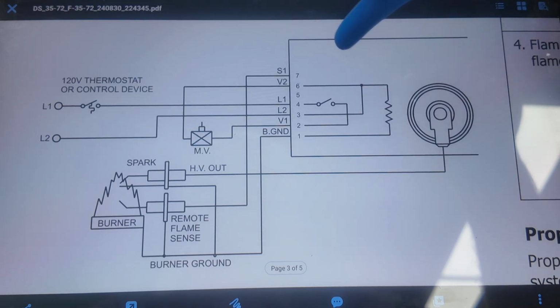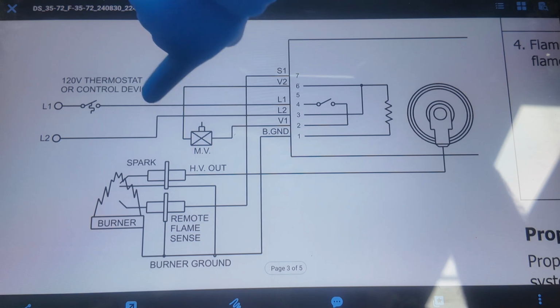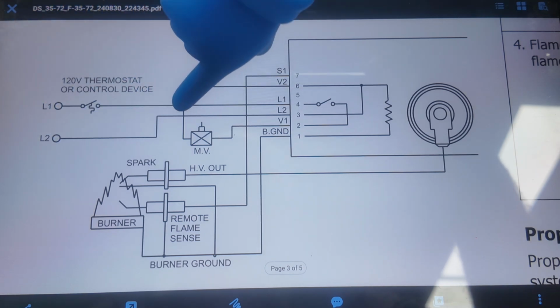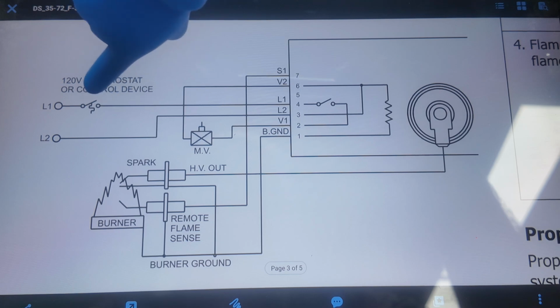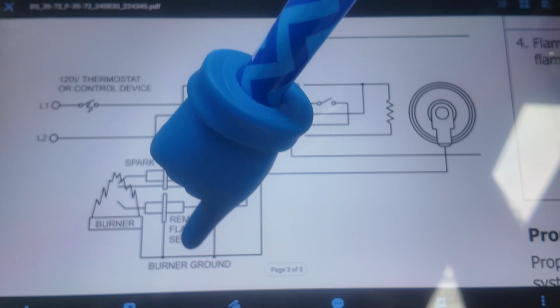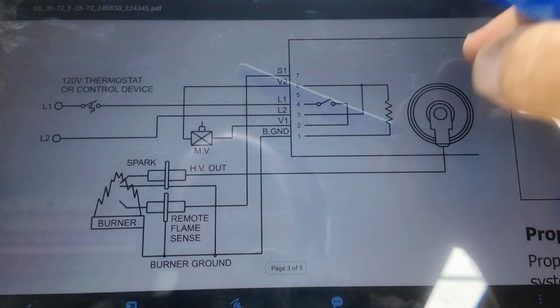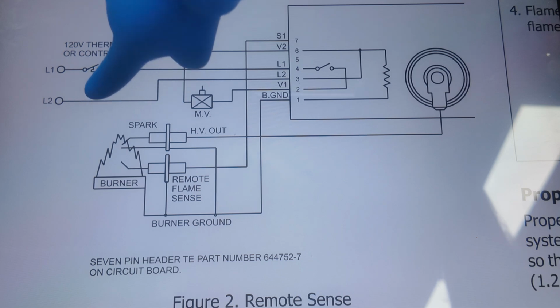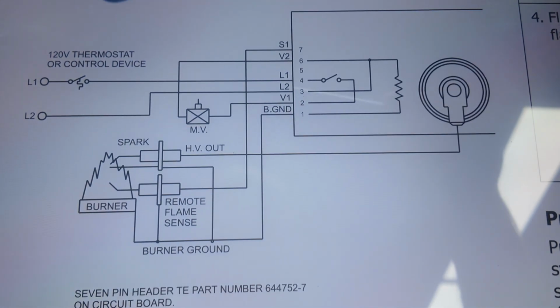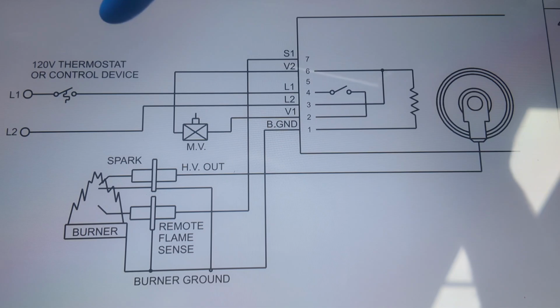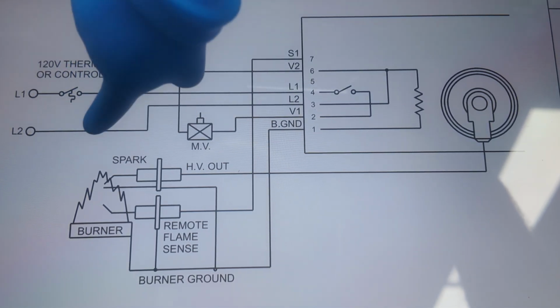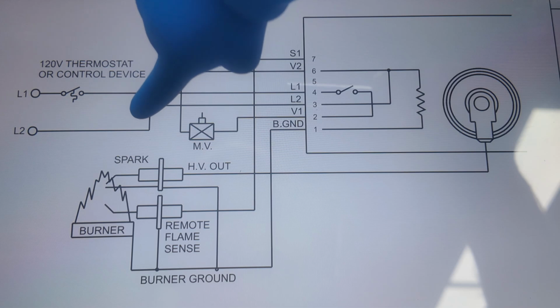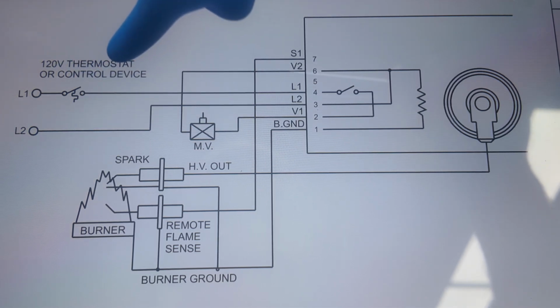So at that point, we need to look at, is our voltage correct? Is L2 neutral? Is L1 115 volts? What's the difference in voltage between L2 and your ground? What is the difference between L1 and L2? Because we need 115 volts. If you have 90 volts, it's not going to work. If you have 180 volts, it's not going to work.